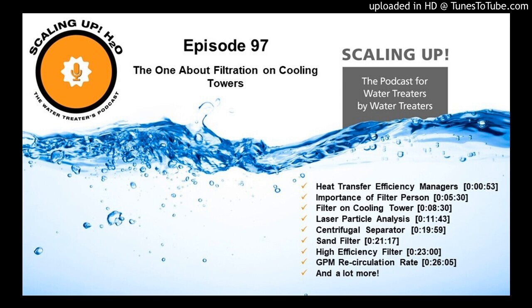So if this is my account and I'm going in there to look at the cooling tower, maybe looking in the sump to see what that looks like, or looking at a history of corrosion coupon analysis, is there any evidence that deposition is causing a problem with the customer? When he brushes his tubes, during the once a year shutdown that most people have, do the tubes have that little slimy feel in them? Because biofilm is the main cause of deposition problems in cooling systems, because that's where all of the bacteria grows and nucleation for more settling happens, things like that. And it builds up a film on the tube surfaces or the heat transfer surfaces.